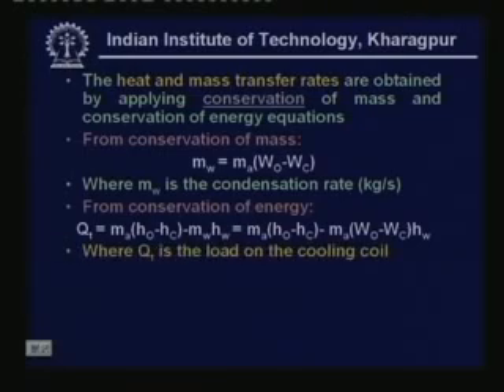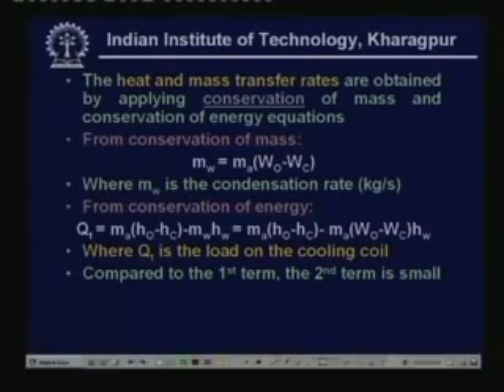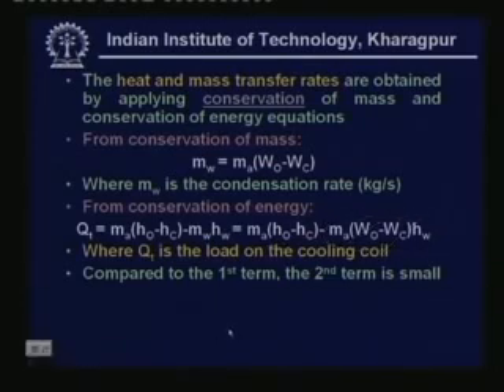Here Qt is the load on the cooling coil, and as I said, H naught and Hc are the inlet and exit enthalpies of air, and Hw is the enthalpy of the condensate, that means enthalpy of the liquid water that is leaving the control volume. Compared to the first term, the second term is generally small, so we can generally neglect this term. Once you neglect this term, you find that Qt is equal to m dot A into H naught minus Hc. So that means simply mass flow rate multiplied by the enthalpy difference.